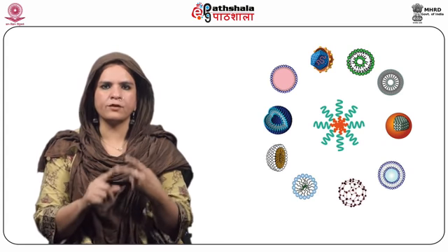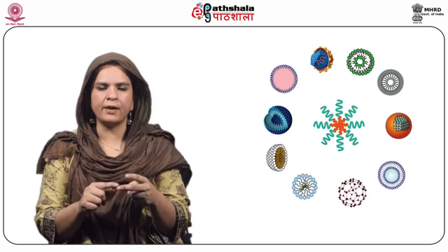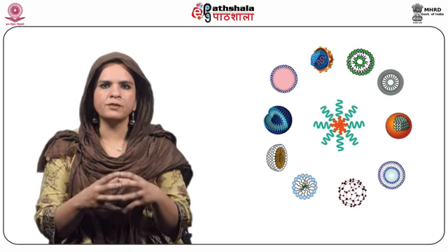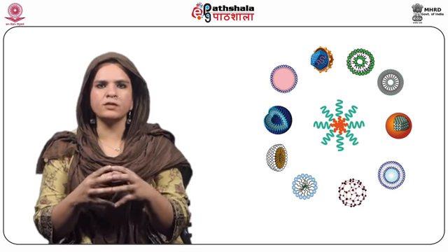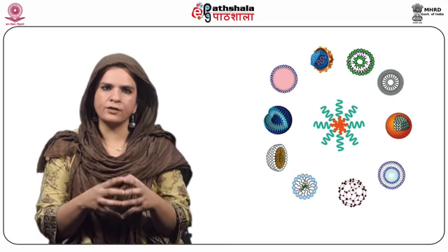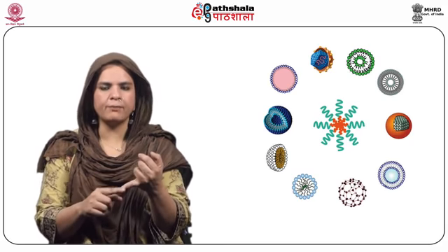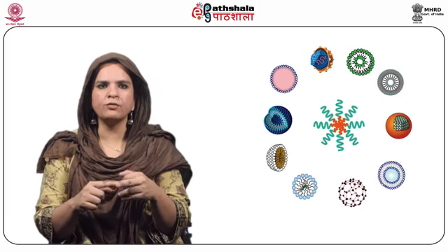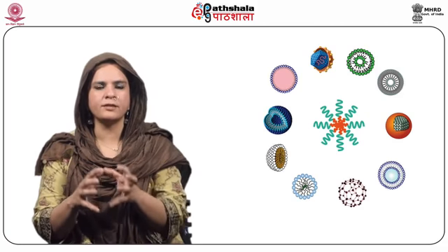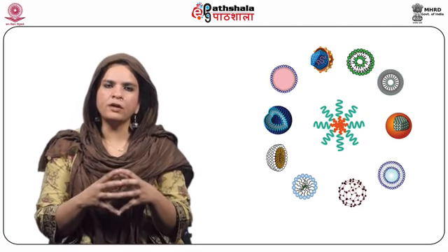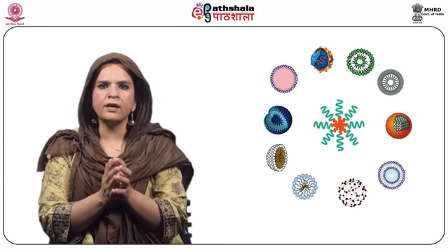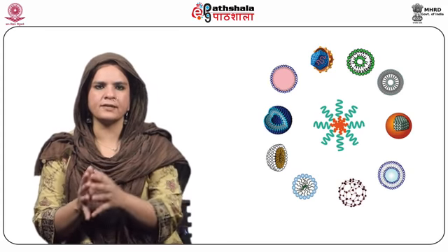Mainly, two types of battery-powered implantable programmable pumps are used successfully for delivering insulin. These are number one, the peristaltic pump, and number two, the solenoid-driven reciprocating pump. Both are controlled electronically to release the drug at the desired site.